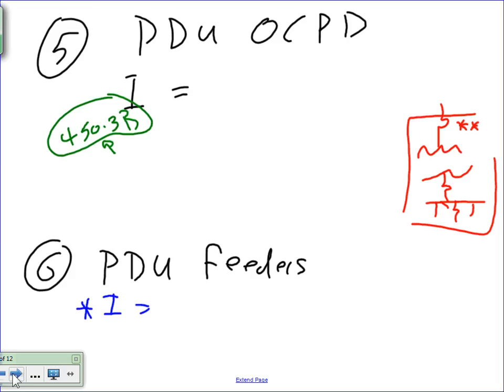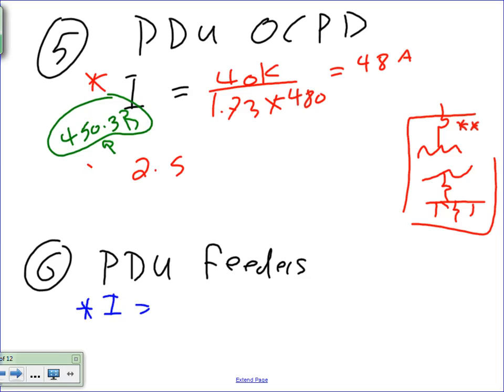Now the PDU overcurrent protection device, number 5. You're going to take the 40 kVA divided by 1.73 times the voltage. What is the input of the PDU? What's the voltage? 480. We're still at the 480 volts, not yet at the 208. So if you go there, it'll give you 48 amps. We did that. Now, Chris, I go to 450.3(B). Why? Because remember, there's a transformer inside the PDU. I want to allow the transformer to start without tripping it, so I use this multiplier. I do 2.5, because of the transformer, from this table, multiplied by 48. Oops, not 480, 48. And that will give me 120 amps.